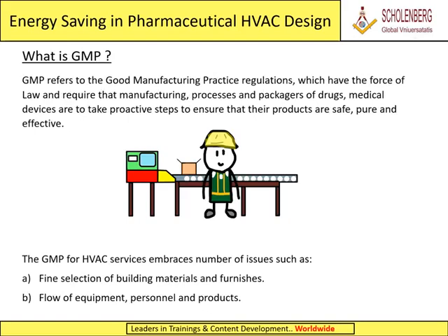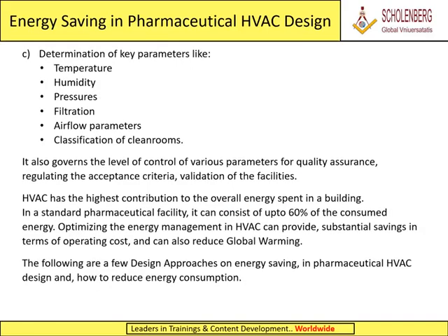What is GMP? GMP refers to the Good Manufacturing Practice regulations, which have the force of law and require that manufacturers, processors and packagers of drugs and medical devices take proactive steps to ensure that their products are safe, pure, and effective. The GMP for HVAC services embraces a number of issues such as: a. Fine selection of building materials and furnishes. b. Flow of equipment, personnel, and products. c. Determination of key parameters like temperature, humidity, pressures, filtration, airflow parameters. d. Classification of clean rooms. It also governs the level of control of various parameters for quality assurance, regulating the acceptance criteria and validation of the facilities.